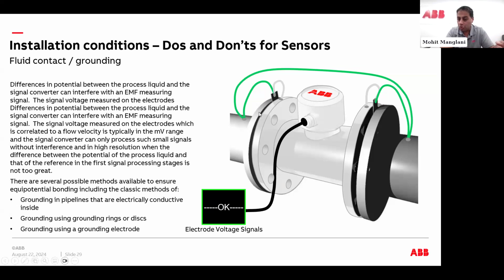Even if you have a surge strike or an event or a surge of power in your power supply, or anything that happens on the line or in your process, the idea is this kind of apparatus, we call this a floating ground, it gets rid of noise and it bypasses the mag meter to prevent any disturbances in your accuracy. So the idea is this is what good looks like on the cross bonding side. And we typically say apply this to every mag meter we sell, whether it be any of ABB's or even we would say to our competitors.